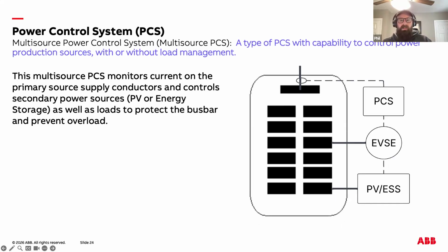This scenario builds on the earlier multi-source PCS example, but now the system is managing both a power-producing source and a significant load, which adds another layer of coordination and control. In this configuration, the PCS is not only regulating the output of the PV ESS system, but is also actively managing an EV charger connected to the same busing.